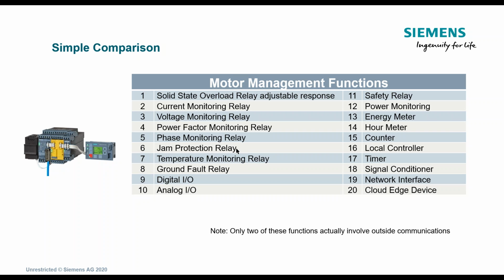Now, if anybody has been around in the electrical business for quite some time, in Wyoming, I had a customer who came to me and said, we can't find this old Westinghouse jam module on eBay. Well, what it was is a reversing contactor, and they didn't care what direction the motor turned as long as it kept spinning. It was a hammer motor application. They didn't care if it was spinning clockwise or counterclockwise. But if something jammed up the rotation and wedged in there, they didn't want it to trip.